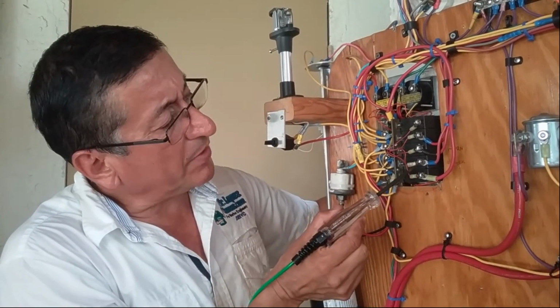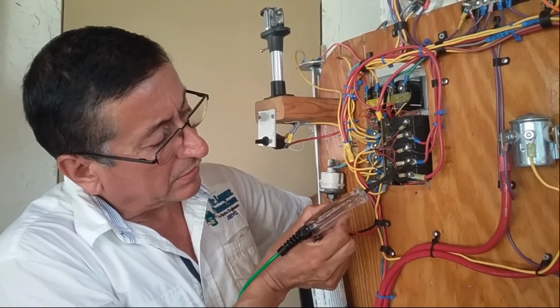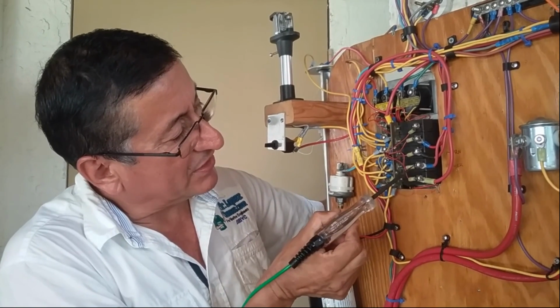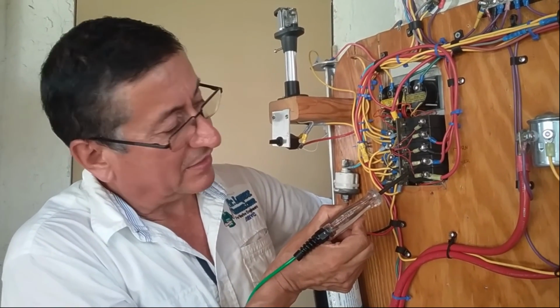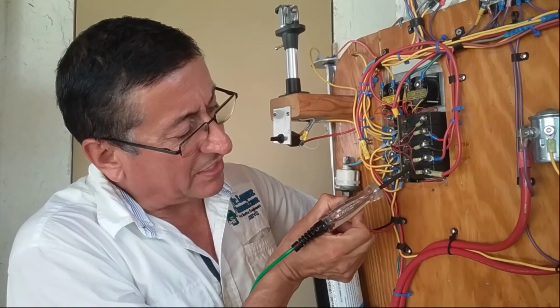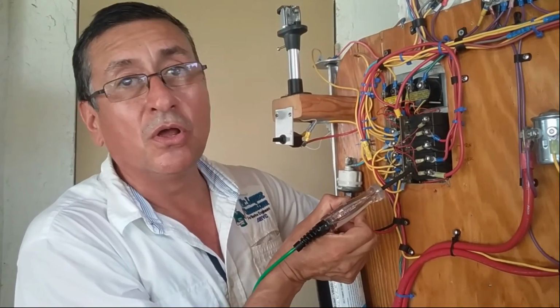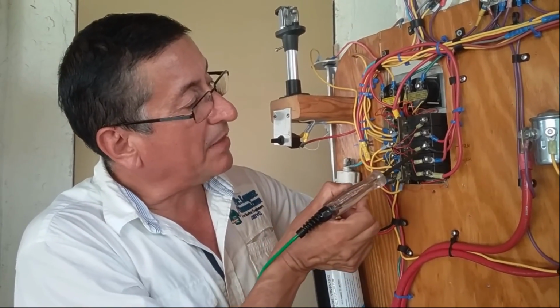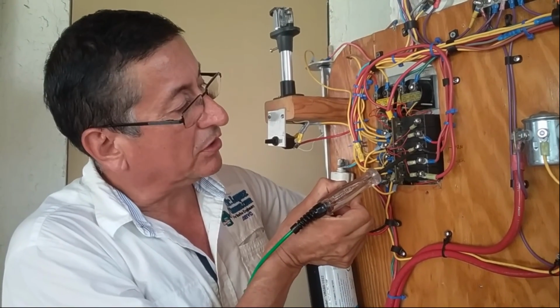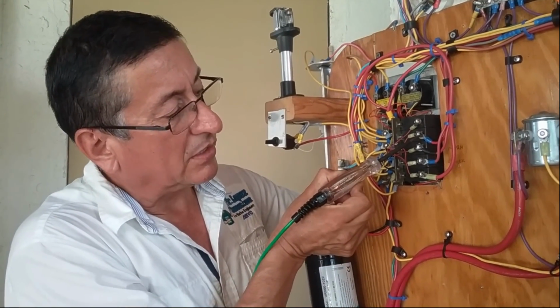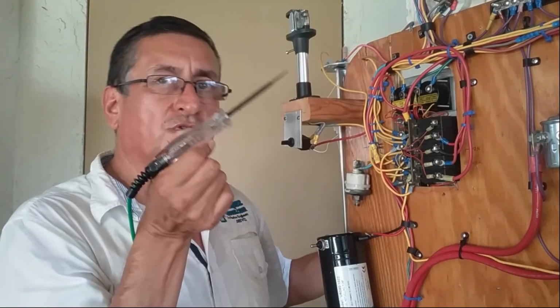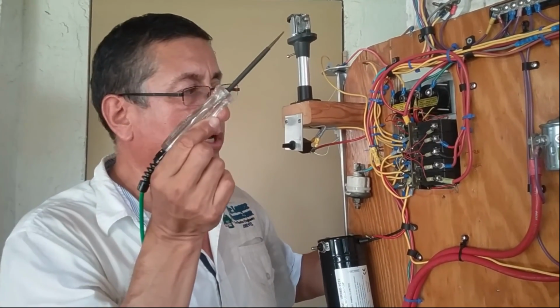Let me check if the second breaker is working. Oh, that breaker is damaged. You check? Oh, it's working intermittently. Sometimes yes, sometimes no. Okay, I need to replace that breaker. Let me check this breaker. Oh, that's good. Let me check this. Okay, that's the procedure to check if the breakers are working.